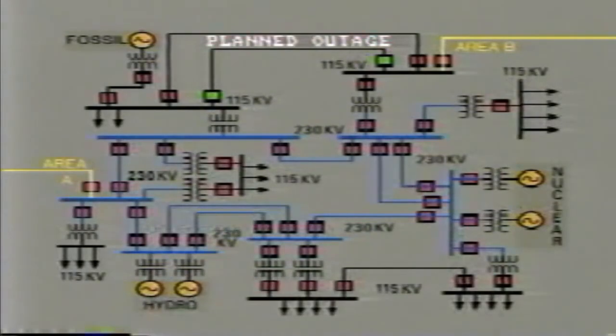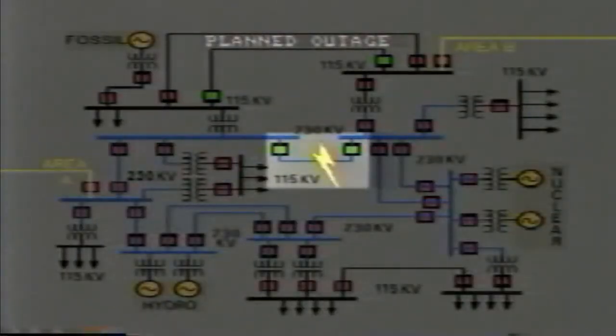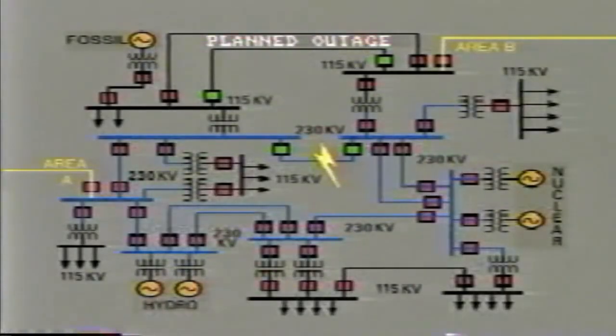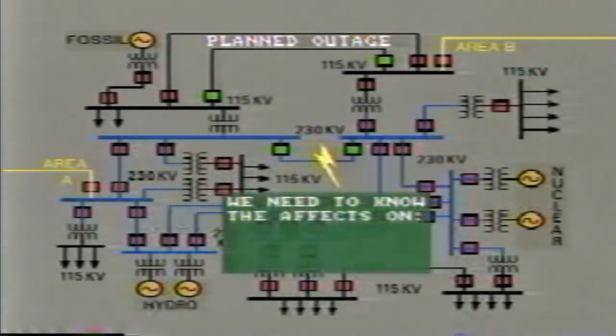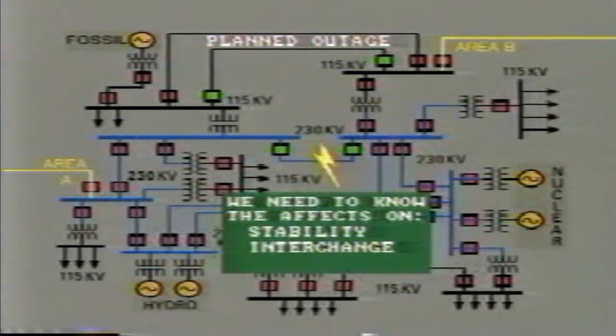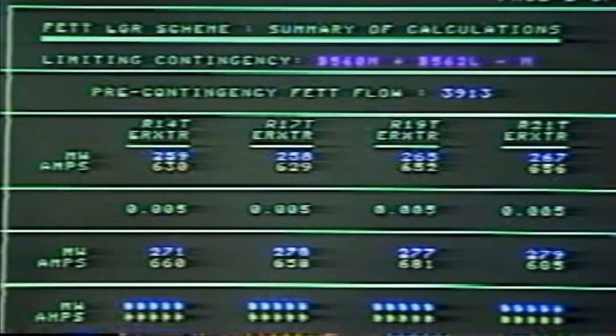system significantly. However, the system operator has to be concerned with the possibility that while the system is operating in this weakened condition, a sudden forced outage may occur. This could be, say, an interruption due to a fault tripping a transmission line out of service. So we need to know just how this hypothetical second outage would affect the stability of the system, the interchange, and the voltage. These what-if questions are answered ahead of time by examining many different hypothetical situations through what is known as a contingency analysis. The answers are tabulated for ready reference by the operator, usually on a computer screen.